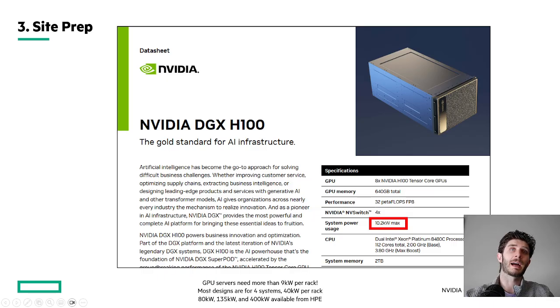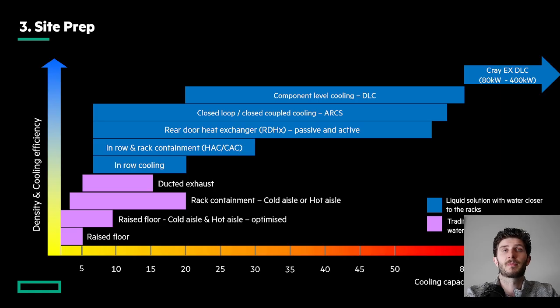Why does this matter? Because individual systems with 8 GPUs are massive power hogs. The DGX H100 is rated at 10.2 kilowatts, and HPE's HGX H100 system, the XD670 or XD685, consumes similarly. As we build for more powerful GPUs for Blackwell and beyond, there's going to be more power consumption over time. GPU servers need more than 9 kilowatts per rack. Most designs we have are for 4 systems, 40 kilowatts per rack, but there are designs for 80, 135, and 400 kilowatts per rack available from HPE.